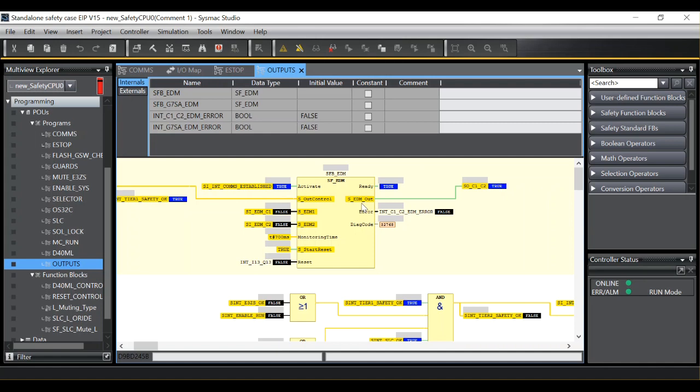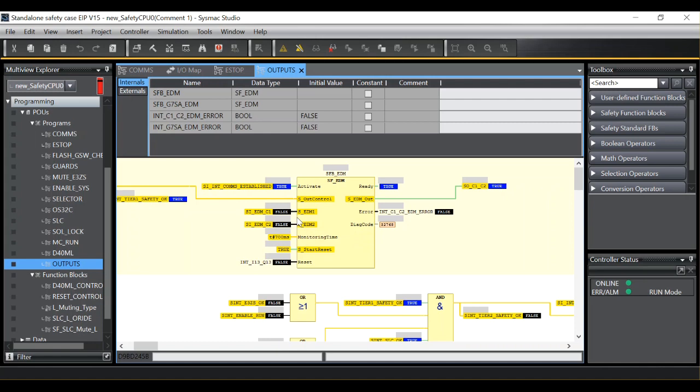It is used to dynamically check the status of a feedback signal in relation to an output. For example, often the input signal will be from a normally closed contact on a contactor or dump valve. The function block expects to see a logic 1 on EDM 1 and EDM 2 if the safety output is at logic 0.